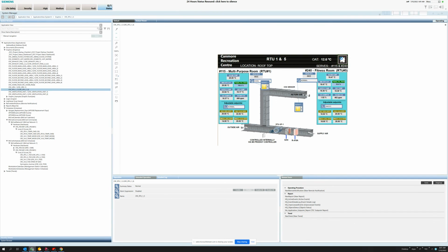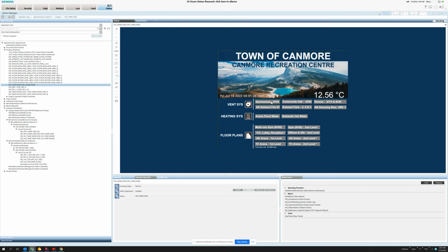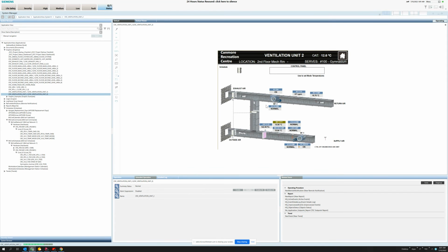The other thing I found a little odd is so on gymnastics, even though this one's asking for 12 and the outside air temperature is 12, the damper position's only at 43%. Whereas I would assume if you've got 16-degree air, you wouldn't want to mix that air with your 12-degree air if you're trying to get to 12.